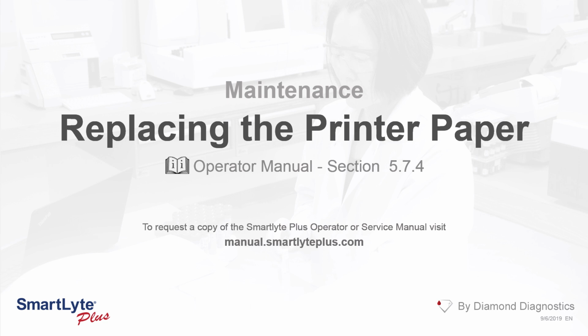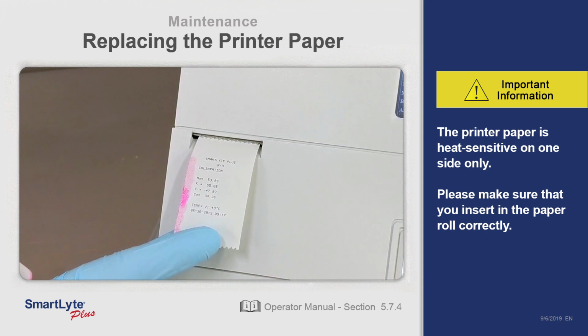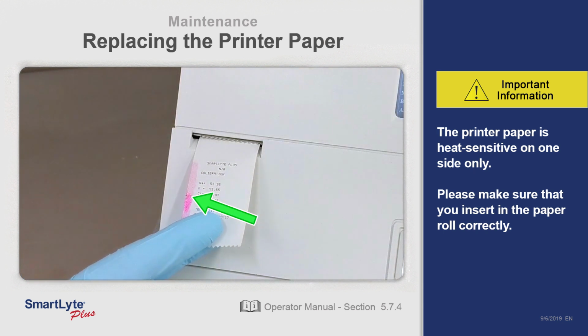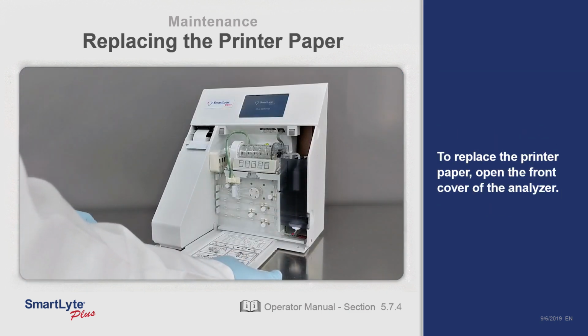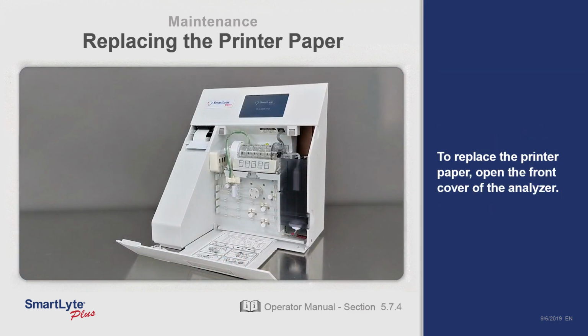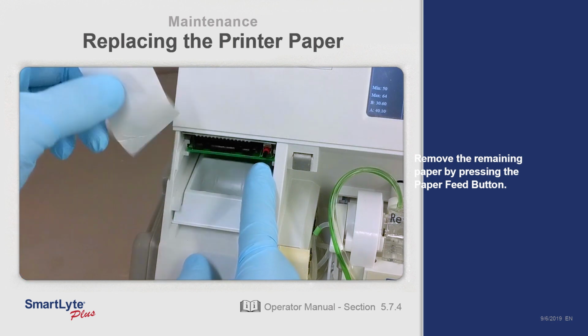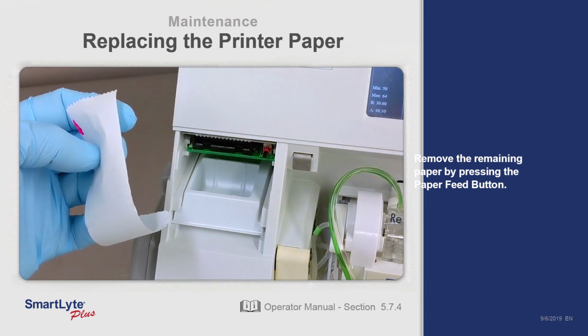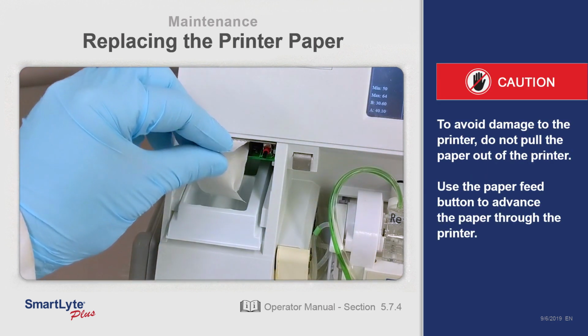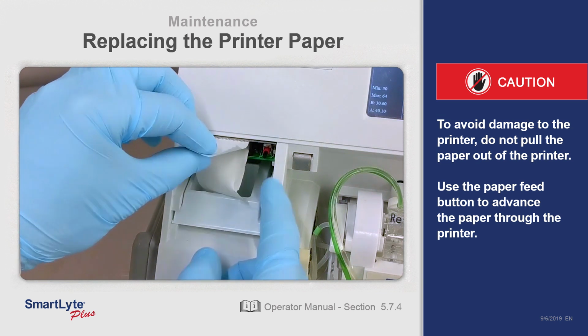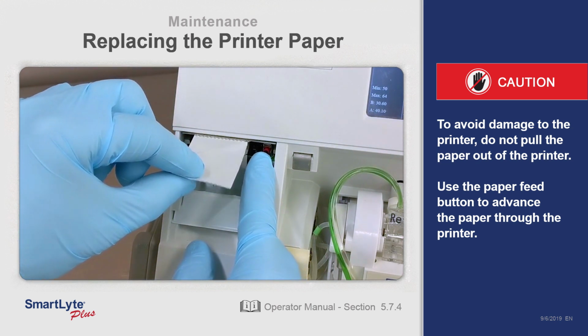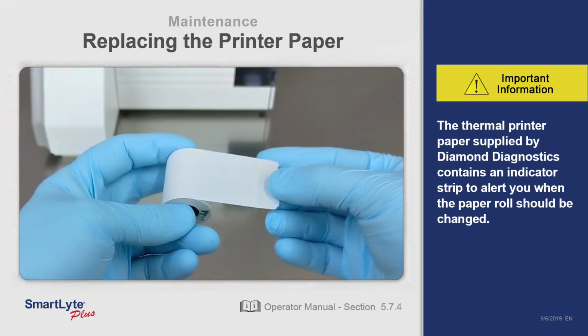Replacing the printer paper on the SmartLyte Plus. The thermal printer paper supplied by Diamond Diagnostics contains an indicator strip to alert you when the paper roll should be changed. To replace the printer paper, open the front cover of the analyzer. Remove the remaining paper by pressing the paper feed button. To avoid damage to the printer, do not pull the paper out of the printer. Use the paper feed button to advance the paper through the printer. The printer paper is heat sensitive on one side only. Please make sure that you insert the paper roll correctly.